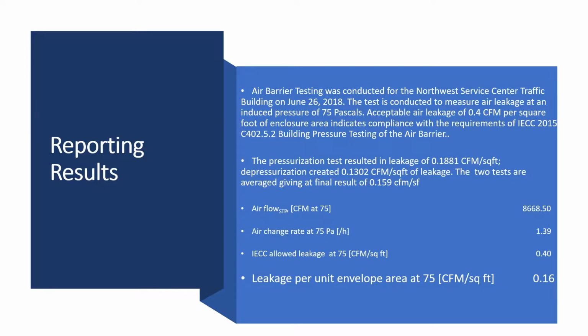Now that does seem like a lot of air, but it's a pretty good sized building, and it's based on the cubic feet of volume within the building. We have an air change rate of 1.39 per hour, so the entire building in 1 hour will exhaust itself 1.39 times. So that is a pretty low leakage rate. The IECC allowed leakage rate is 0.4, and our flow per unit of area at 75 pascals was only 0.16.